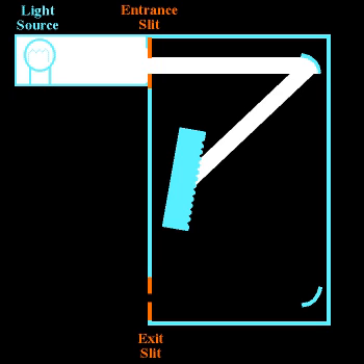This mirror reflects the incoming light, now shaped like the entrance slit, and collimates it to fall on the grating. In older instruments, a prism would be used instead of a grating. The collimation process makes all the light rays reflected onto the grating parallel to each other, so they do not diverge as they travel from the first mirror toward the grating.